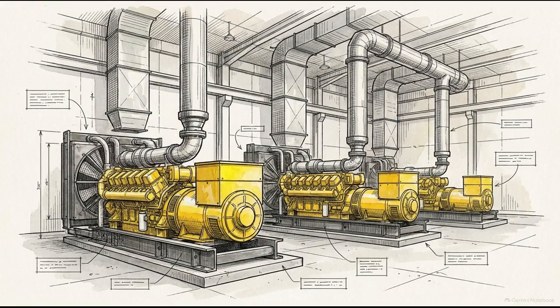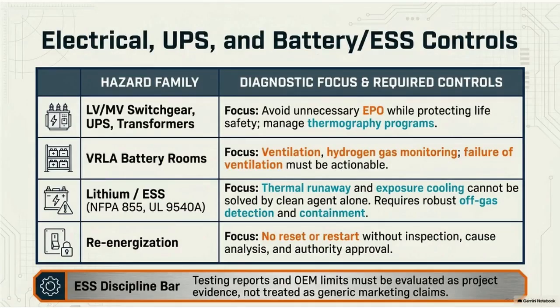The IT equipment relies on a massive footprint of support infrastructure, and these mechanical and electrical zones present entirely different fire profiles. This matrix breaks down electrical hazard families. The diagnostic needs for a traditional VRLA battery room focus heavily on ventilation and hydrogen gas monitoring, which differs significantly from a modern lithium-ion energy storage system. In lithium-ion environments, clean agent suppression alone cannot solve thermal runaway or exposure cooling. These systems demand robust off-gas detection and physical containment strategies dictated by NFPA 855.